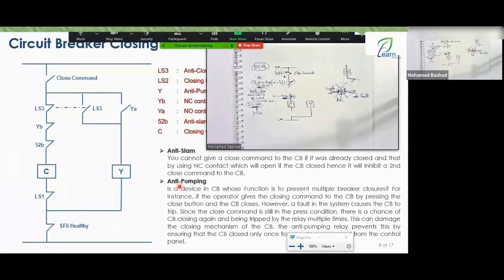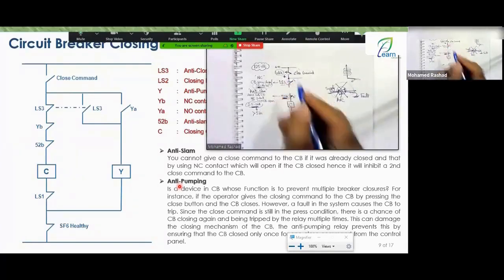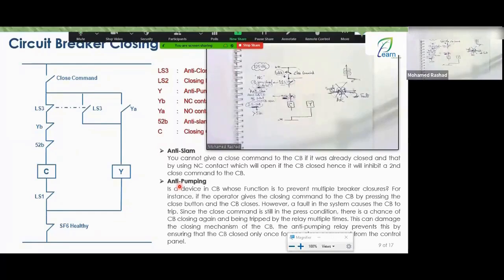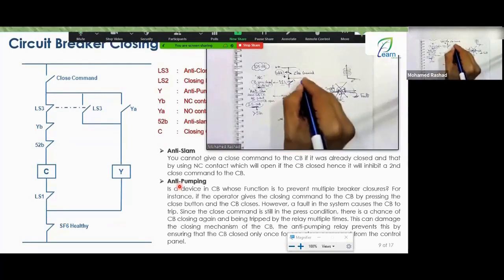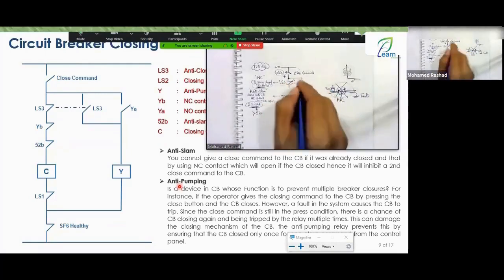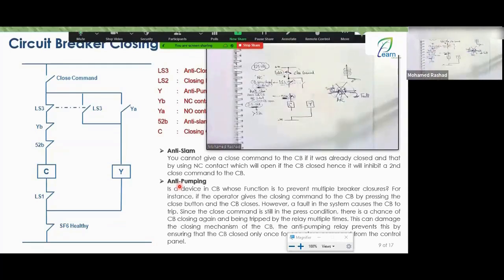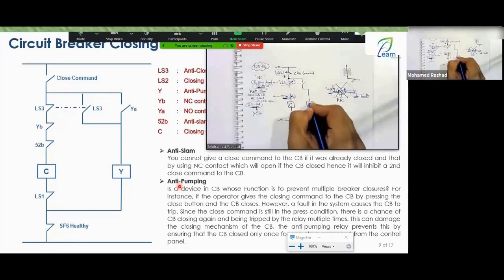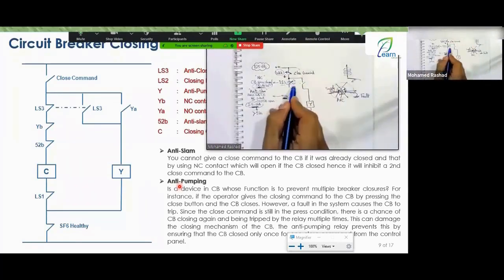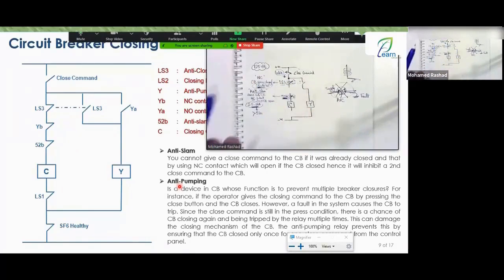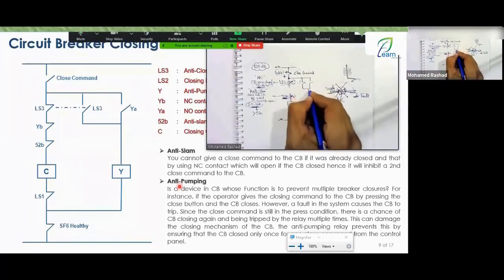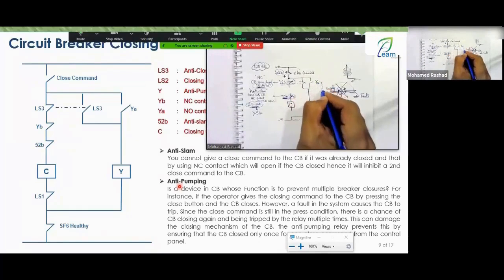Focus with me. It comes here from the DC and moves like this. It tells you that as soon as you close the power cut, what happens? Doesn't the limit switch of the spring open as a result of the spring discharging? I said yes. He said, okay, I will also take the limit switch S3, take another contact, and connect it here to this coil. So as soon as you close the power cut, this one opens and this one closes. Okay, after the spring charges, this will return closed and that open, right? So I will make another move. Didn't this close and activate the Y wire? Yes, he told me to take a contact from this same Y, which is a normally open contact.